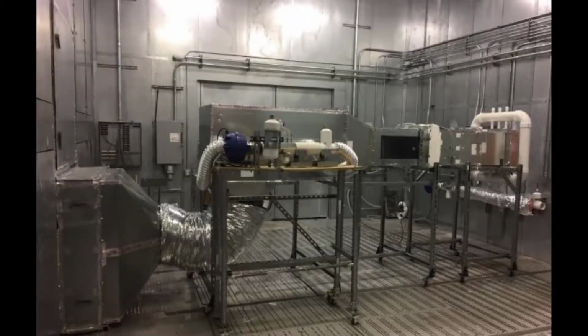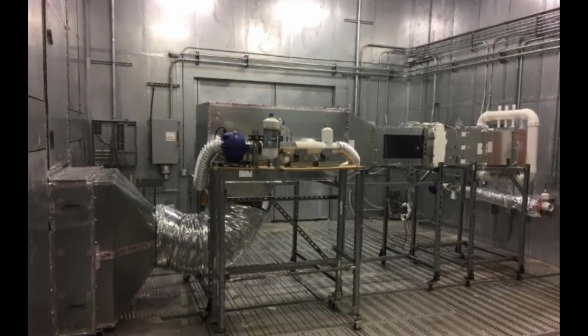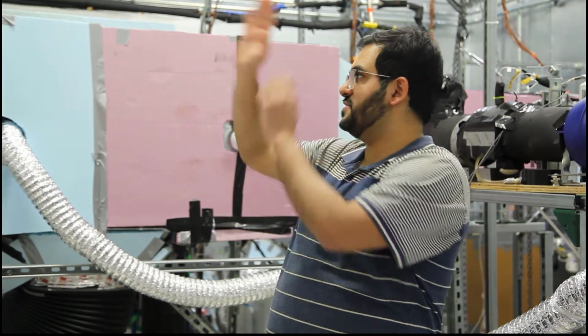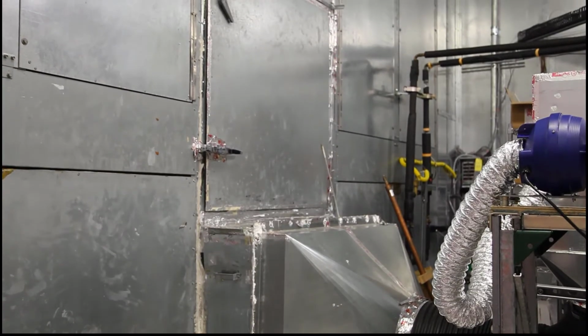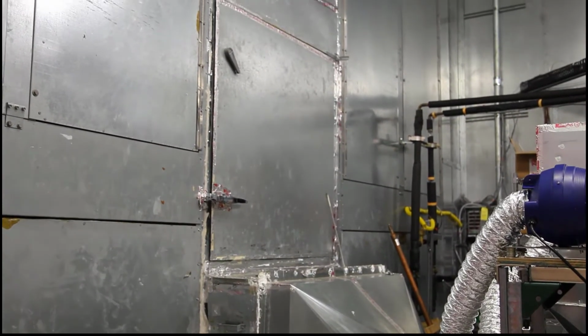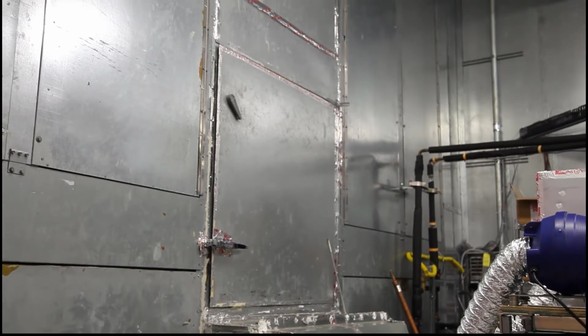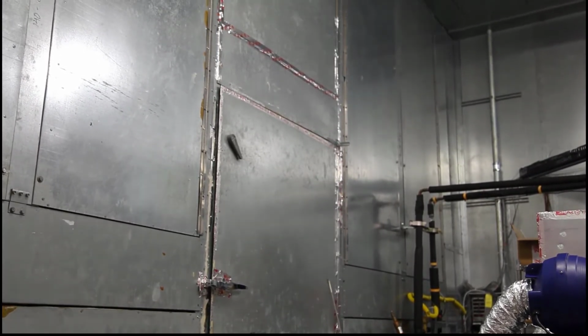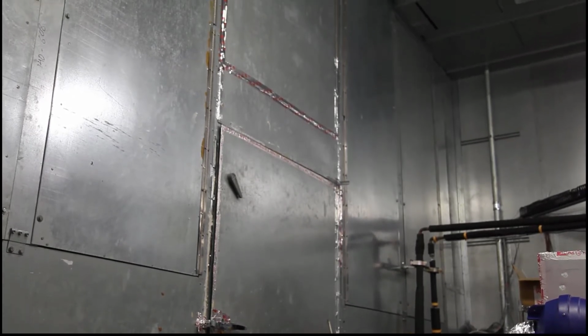I would like to point out here that the psychrometric chamber facility is able to achieve the air side inlet conditions, that is temperature and relative humidity, by a combination of electric water heaters, a chilled water loop, a set of fans, and a steam generator. Behind me here you see a combination of 3 different bays. Bay 1 and Bay 3 are identical to each other, and these house the majority of the conditioning equipment, while the central bay houses the airflow measurement device.